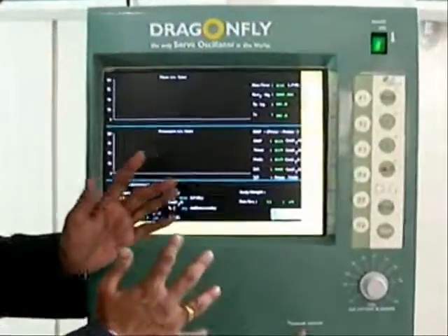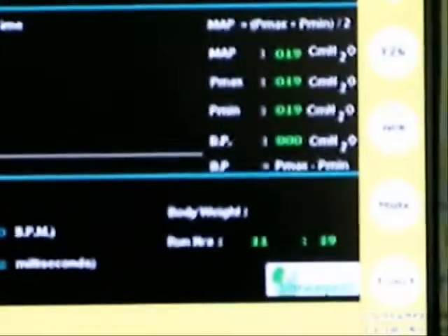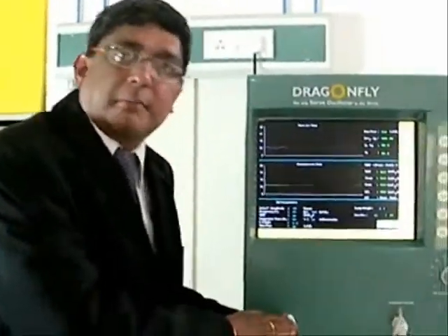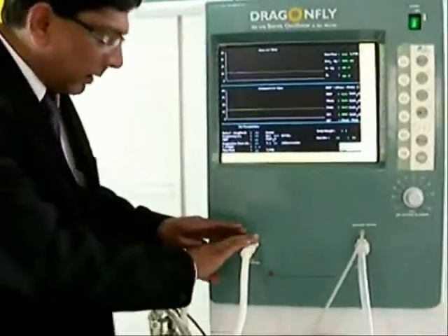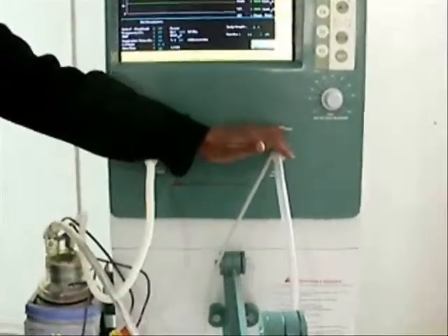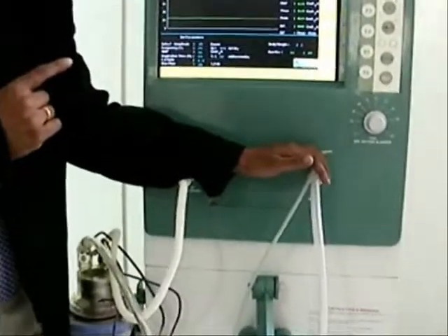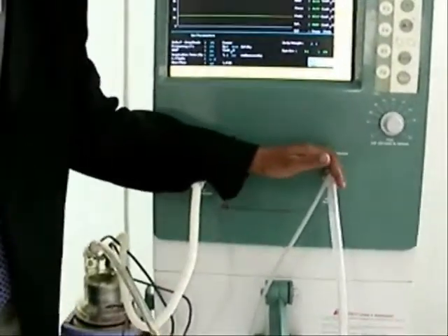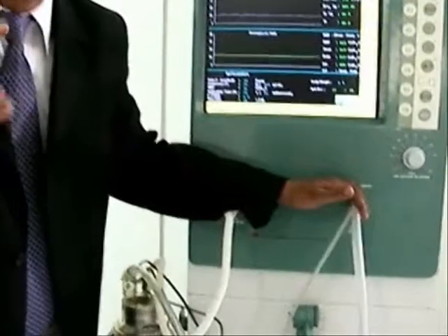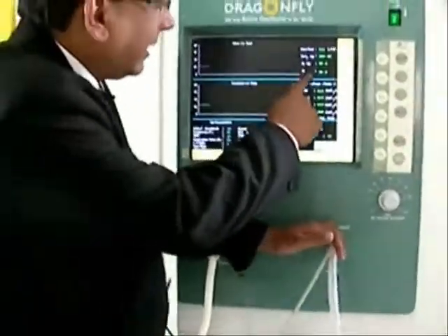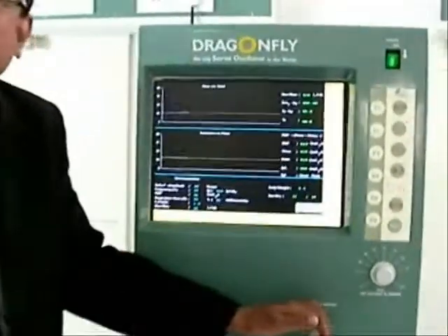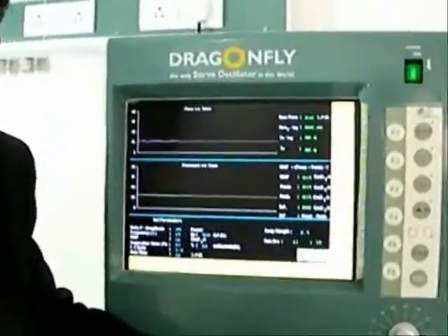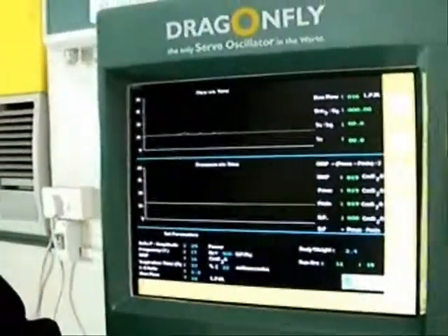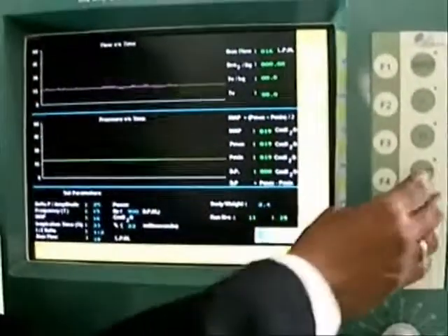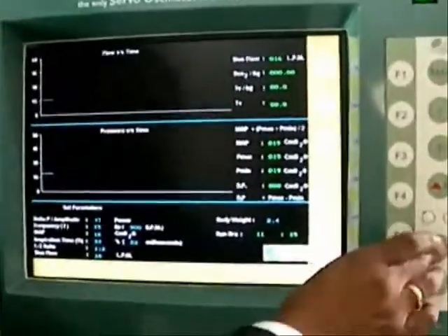In this equipment, we have two flow sensors incorporated in the machine. One flow sensor is at the inspiratory limb, and the second flow sensor is at the expiratory limb. So it senses the flow, calculates the flow 200 times per second, and thus it decides and indicates the tidal volume that is delivered to the patient. Tidal volume again depends on the patient's body weight. So here you enter the patient's body weight. After setting the amplitude, press enter.